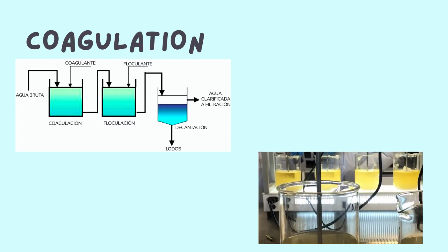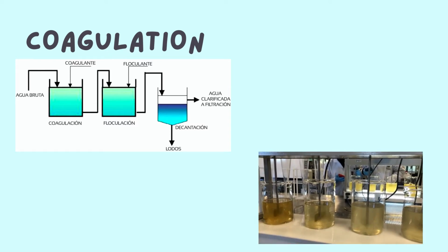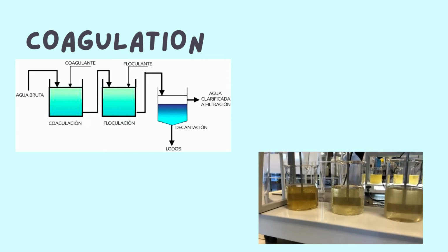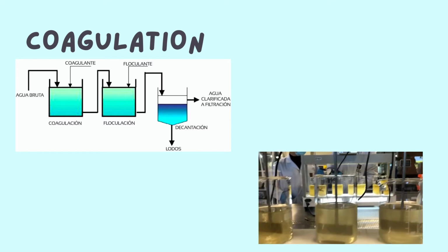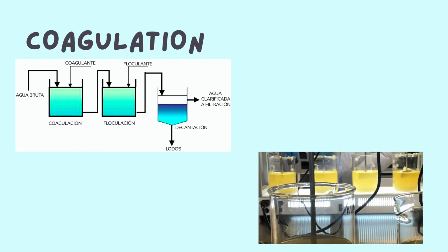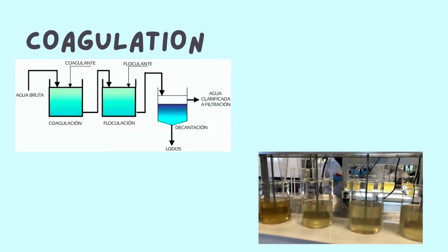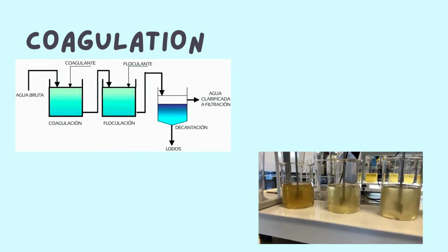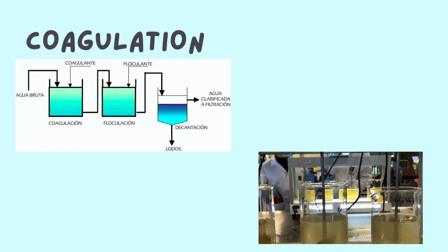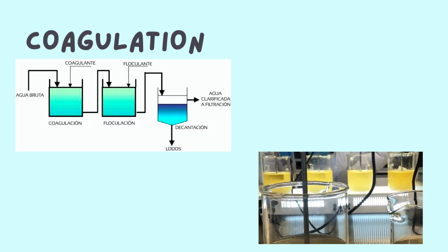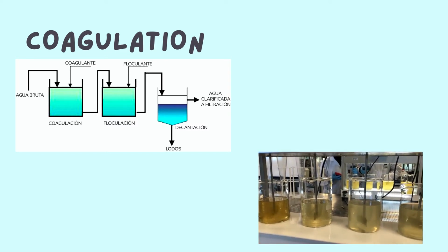On the other hand, our second phenomenon present in one of the unit operations is sedimentation with a coagulation agent and flocculation. The coagulation neutralizes charge and forms a gelatinous mass that traps particles, increasing their size so that sediment can be trapped. Flocculation gently moves or agitates such particles, causing them to coagulate into large masses that settle more easily.